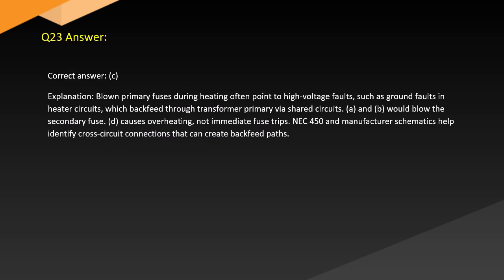Answer. Correct answer: C. Explanation: Blown primary fuses during heating often point to high-voltage faults such as ground faults in heater circuits, which backfeed through the transformer primary via shared circuits. A and B would blow the secondary fuse. D causes overheating, not immediate fuse trips. NEC 450 and manufacturer schematics help identify cross-circuit connections that can create backfeed paths.